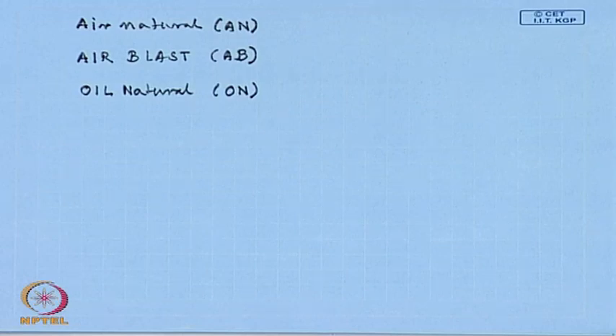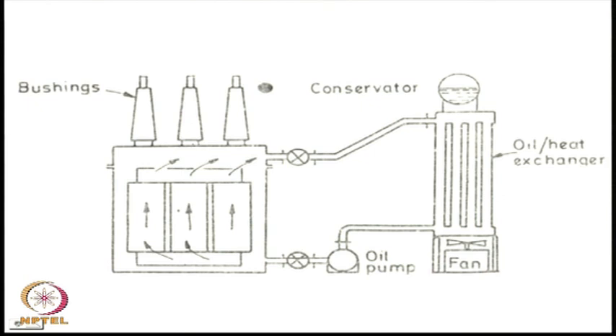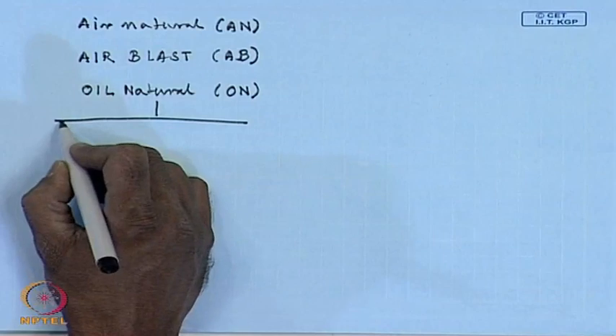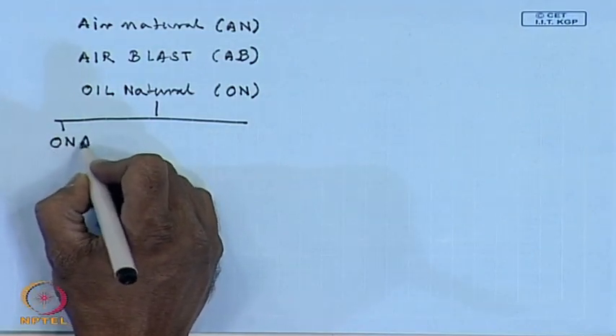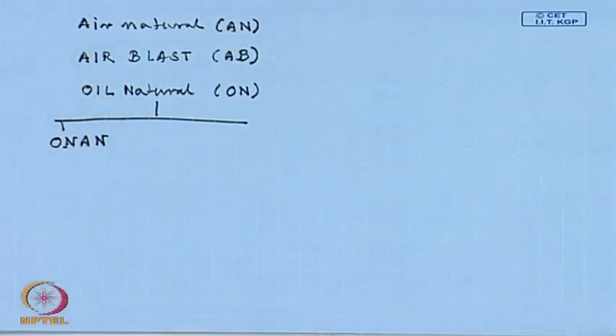For smaller rated transformers, a simple transformer tank is sufficient to provide this cooling. However, for larger transformers, the surface area provided by the tank alone is not sufficient, and therefore the tank's area is usually supplemented. The tank surface is corrugated to increase its surface area. More commonly, circular or elliptical tubes are placed all around the transformer tank in order to increase the cooling area. These are several categories. This is called oil natural air natural, because neither the oil nor the air is forced through any pump or any other device.